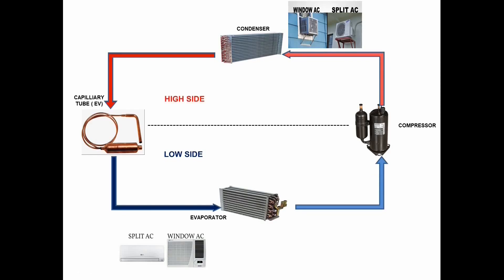The other one is the high side. This is the side of our cycle where the refrigerant is flowing under high temperature and high pressure condition. As you can notice, it starts at the discharge of our compressor, going to the condenser, then before entering the capillary tube. That's our high side.